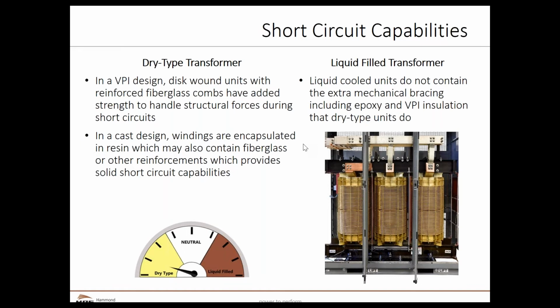With dry type transformers, generally speaking, the actual physical construction and the way we use those varnishes to glue and hold everything together does provide some significant mechanical bracing in the event of a short circuit that you typically don't have in a liquid transformer or liquid cooled transformer. Therefore, a dry type transformer does have some advantages in being able to withstand short circuit conditions.